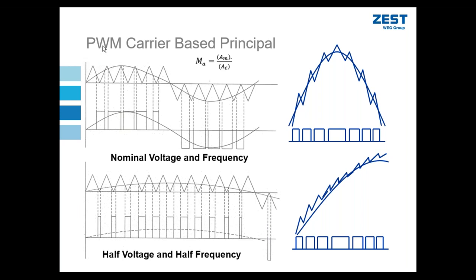One of the simplest methods to switch the DC link voltage to the machine is using a sinusoidal reference and then a carrier waveform. The sinusoidal reference waveform is set to whatever frequency and amplitude you want to provide to the motor. So if we look in this first case on the top, we have, for example, the VSD wanting to supply a 50 hertz voltage to the machine, to the motor. That means this one full cycle is completed in 0.02 seconds.